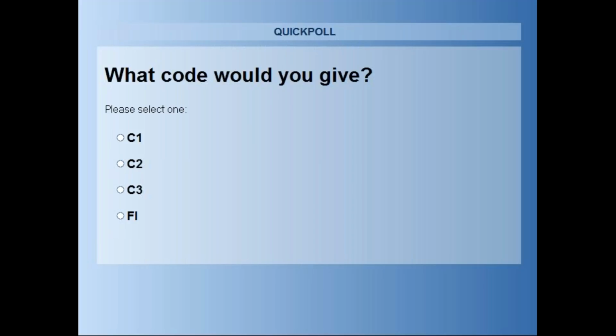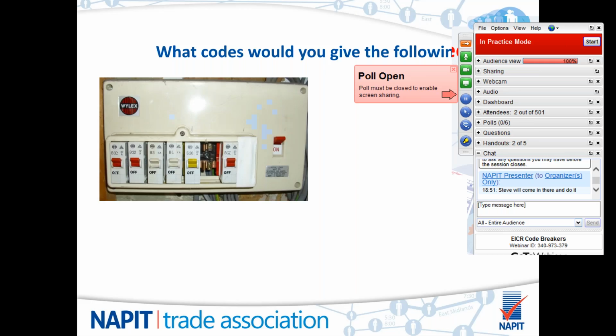So the poll's open at the minute. If you'd like to enter into your panels how you think the issue in front of you should be coded. We'll give you a few more seconds on that one. Okay, most people have concluded, and quite rightly, a very large majority, that this is a C1. Obviously, the bus bar at the bottom is exposed, the fuse carrier is not there, the circuit breaker is not in place. It's a C1.